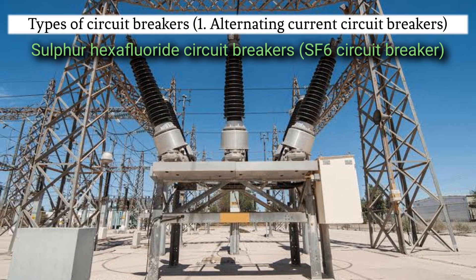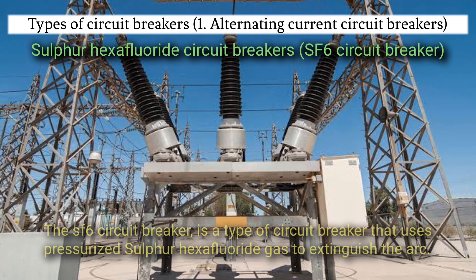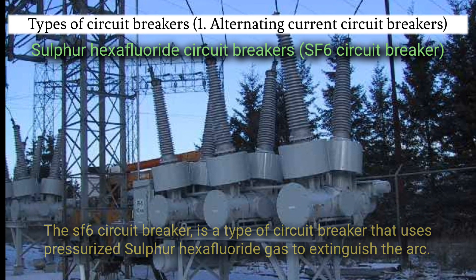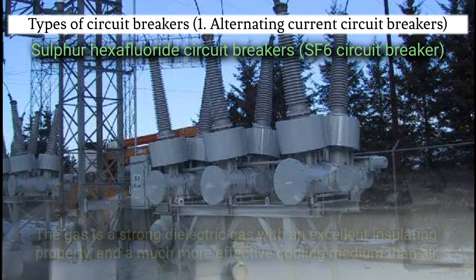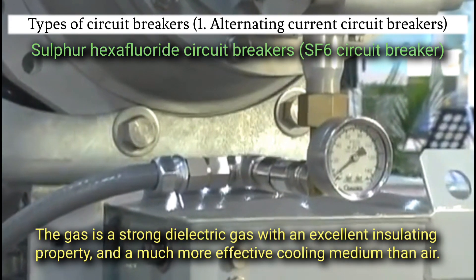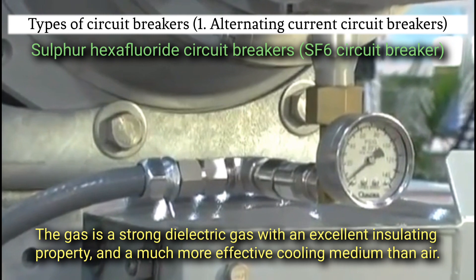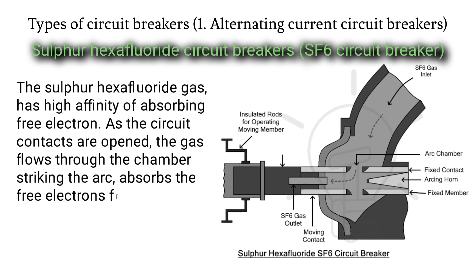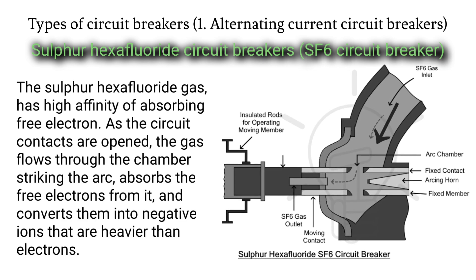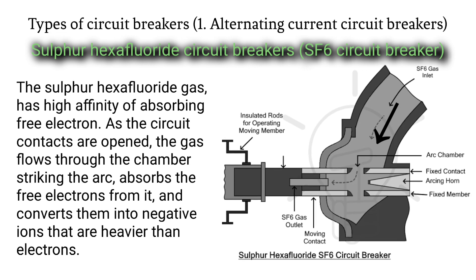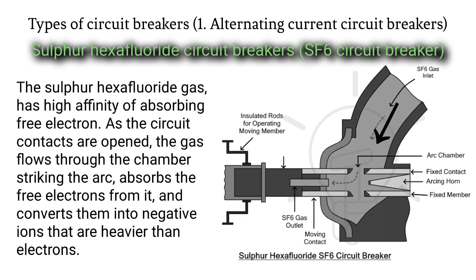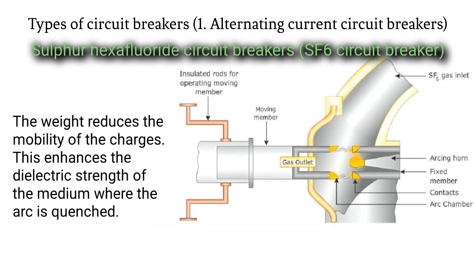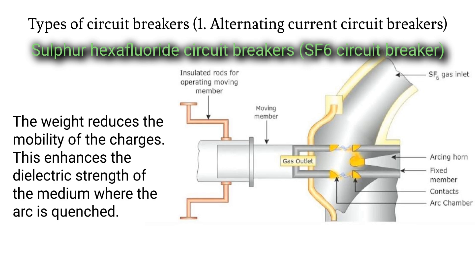Sulphur hexafluoride circuit breakers, SF6 circuit breaker. The SF6 circuit breaker is a type of circuit breaker that uses pressurized sulfur hexafluoride gas to extinguish the arc. The gas is a strong dielectric gas with excellent insulating property and a much more effective cooling medium than air. The sulfur hexafluoride gas has high affinity for absorbing free electrons. As the circuit contacts are opened, the gas flows through the chamber striking the arc, absorbs the free electrons from it, and converts them into negative ions that are heavier than electrons. The weight reduces the mobility of the charges, enhancing the dielectric strength of the medium where the arc is quenched.